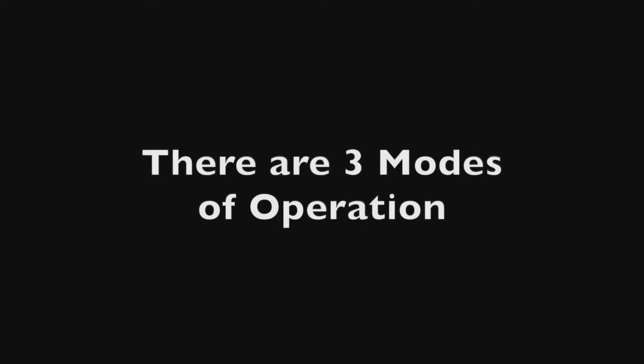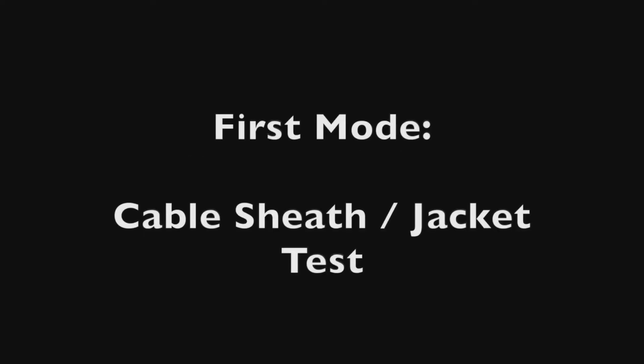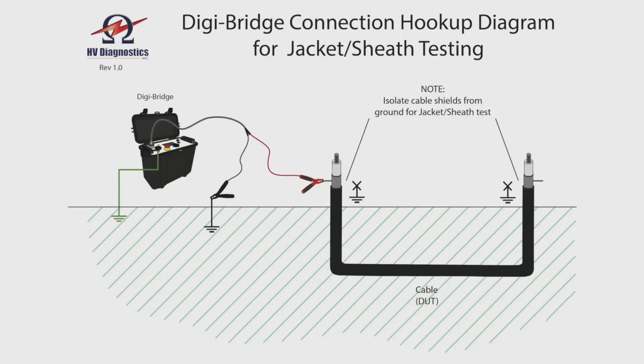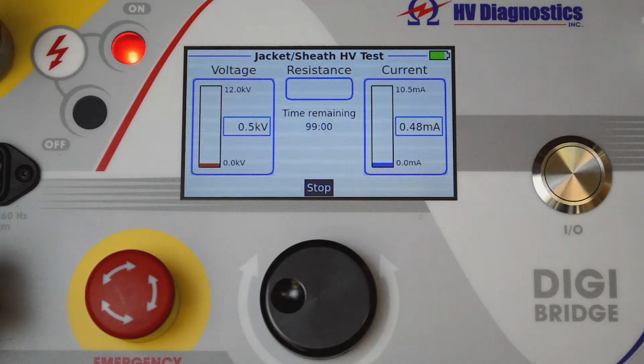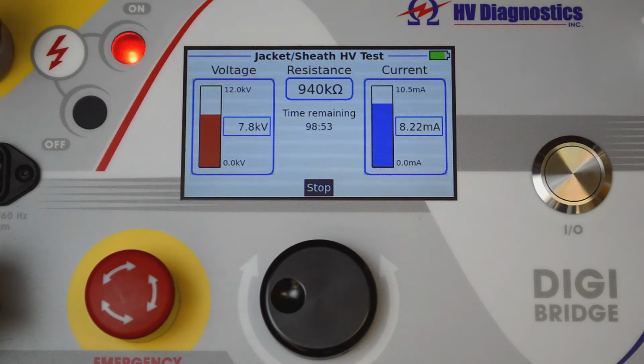There are three modes of operation. The first mode is the cable sheath or jacket test. This test is used for cables that are direct buried or cables that have an outer conductive jacket. The test is very effective and is a pass-fail test, testing the integrity of the jacket. The DigiBridge also has over 10 milliamps of current capability, all the way up to 12 kV of applied voltage, suitable for testing even the very long lengths of cable runs.